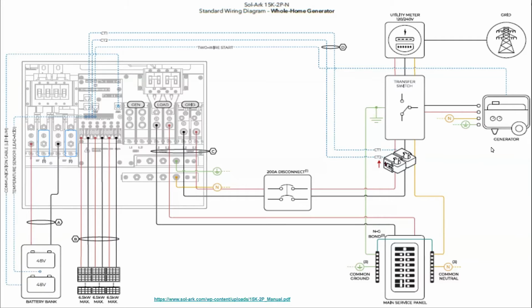So I would recommend to installers to try and avoid the situation of backfeeding through other ways. The first is, accept that, well, maybe the gen port will clip at 19 kW, but go ahead and land the 22 or 24 kW generator on the gen port anyway in a grid tied setting. Or if you have to use that gen port for something else, then when you have external generator controls, only program the generator to run during your non-solar hours.